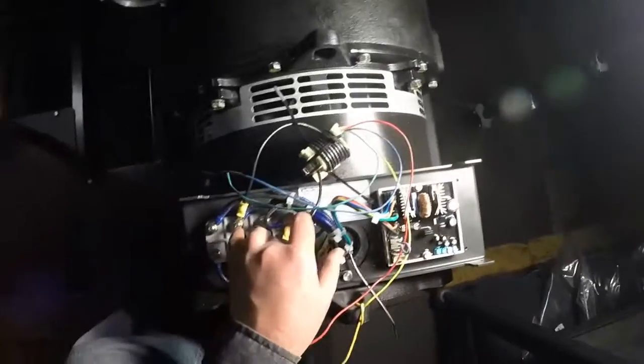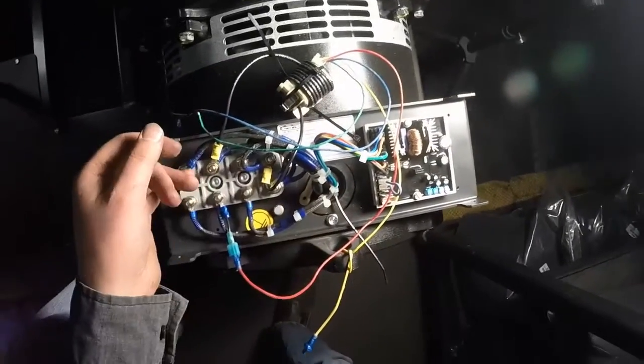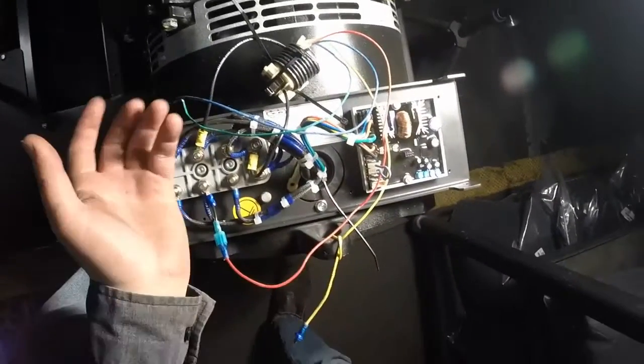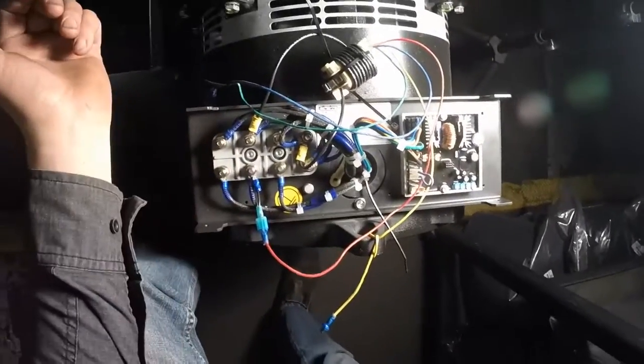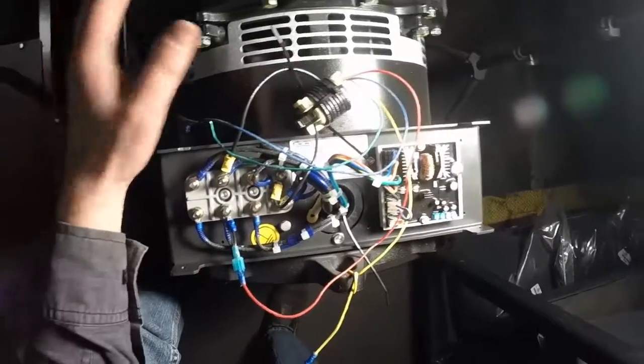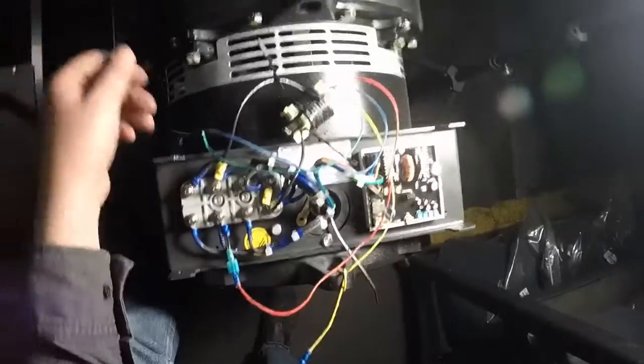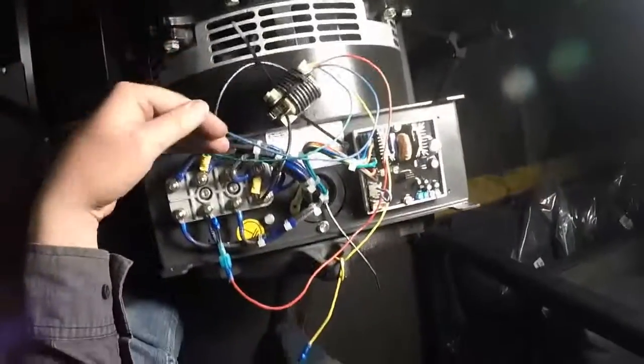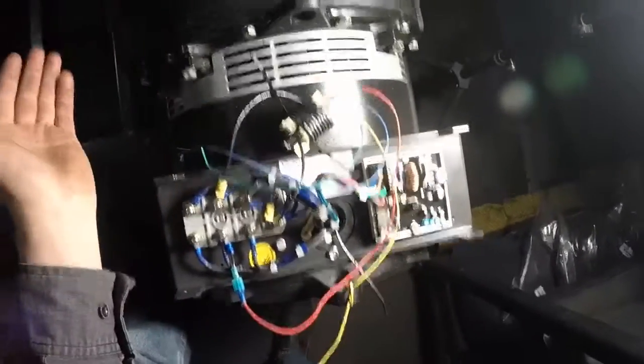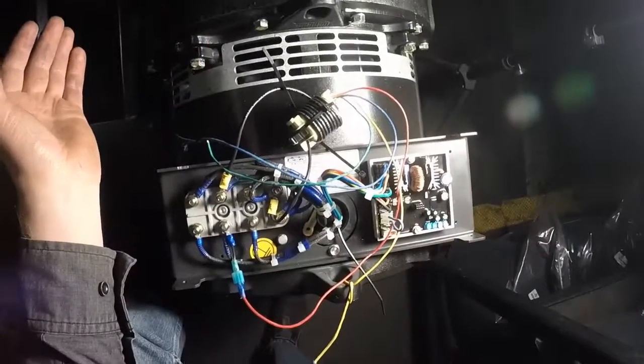And you'll want to make sure that every generator has been tested in that way to make sure that they are all behaving in the same and correct way, which is that you want the voltage to decrease as resistive load goes onto the system.